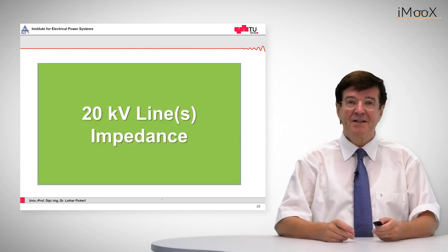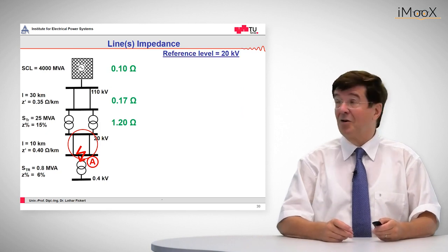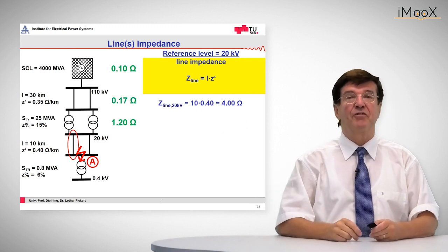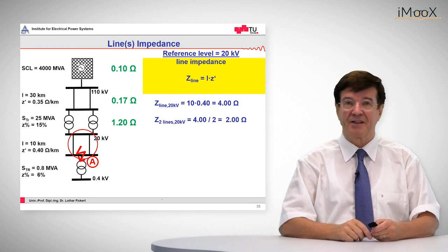The line impedance is calculated as before by applying the law of specific impedance times the length, and we obtain four ohms for one line. We have two in parallel, so the lines all together are two ohms.